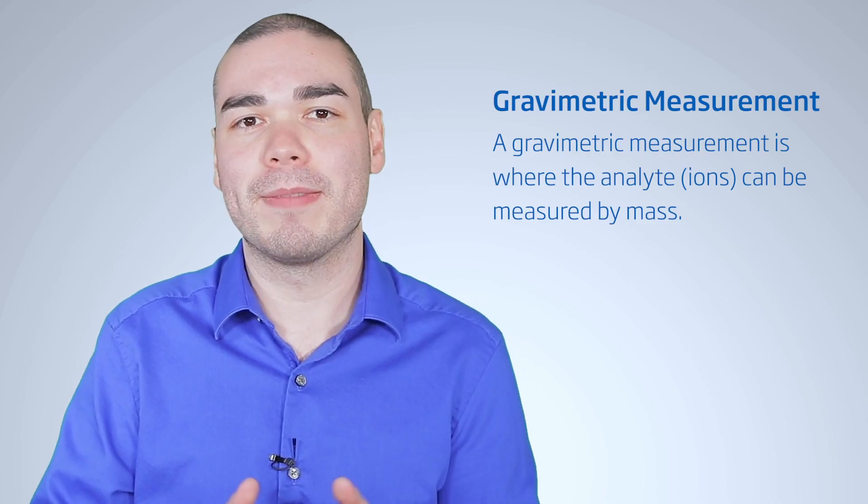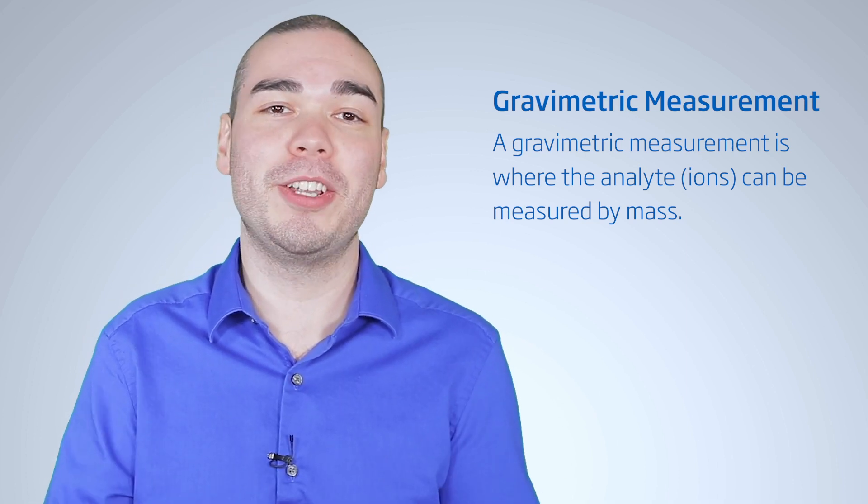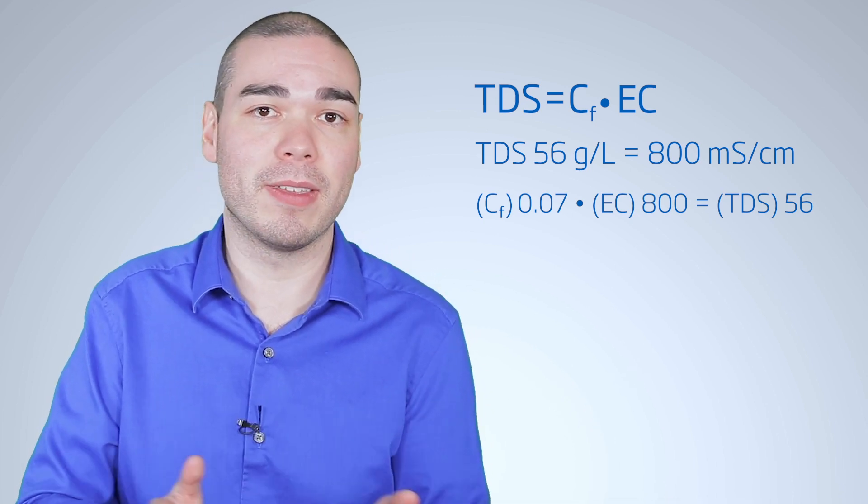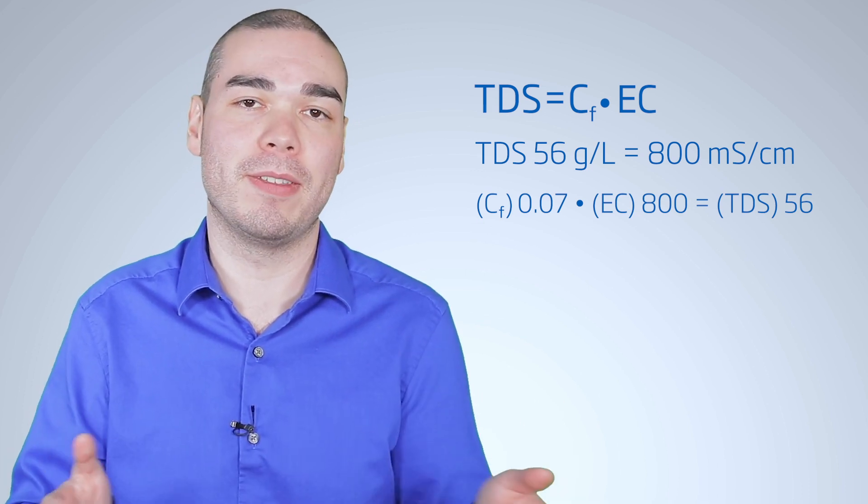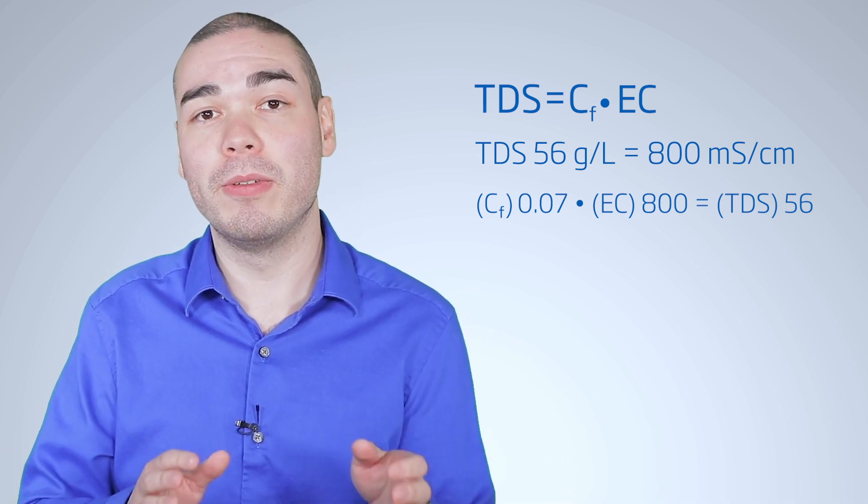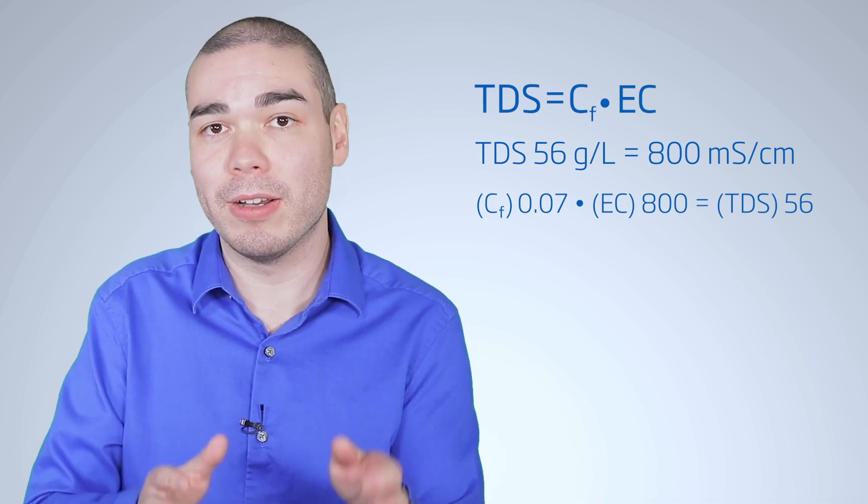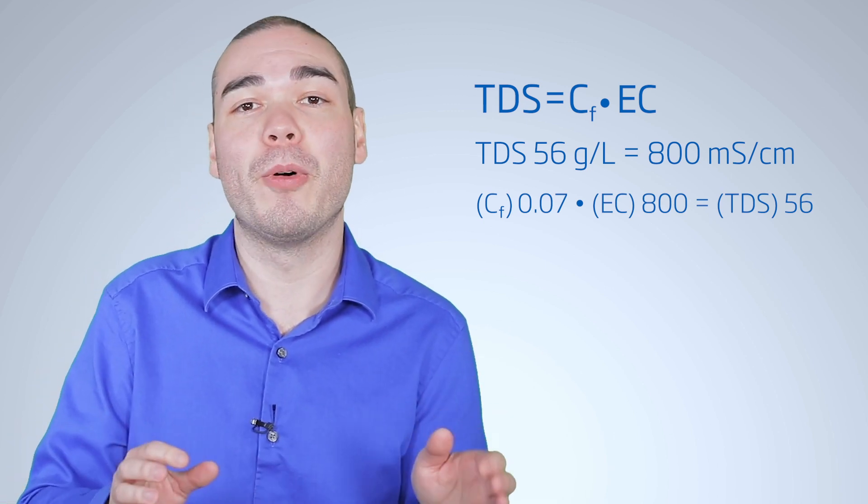This measurement is considered an indirect measurement, as there is a conversion that must be done from EC to TDS. A true TDS measurement is a gravimetric measurement. Every solution has a unique conversion ratio. The conversion ratio is calculated using a known TDS value for the substance, then divided by the measured conductivity value of that same substance. For example, if your solution has a known TDS of 56 grams per liter, and your measured EC was 800 millisiemens per centimeter, then your conversion ratio, or factor, would be 0.07.